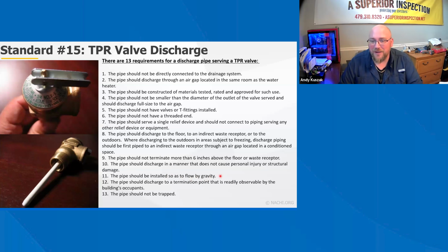The pipe should always flow by gravity. A lot of times you'll find that the temperature pressure relief valve pipe will go uphill where the water heater is shorter than the one that was originally installed. The valve came out of the wall here, but now you have a shorter water heater, so the pipe has to go up to meet the existing pipe. A lot of times the only repair for that is having a plumber open the wall up and pull the pipe down, or raising the water heater up on a landing or a pedestal or something like that. Anything that can stop the water from flowing by gravity easily can potentially lead to the tank rupturing.